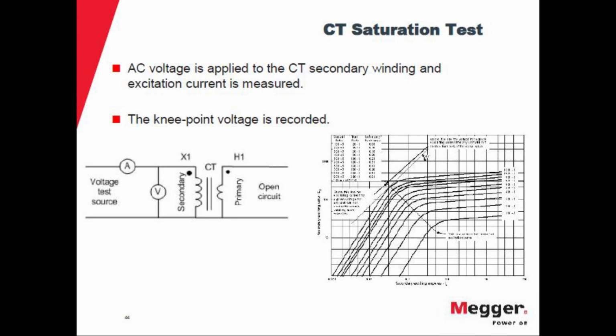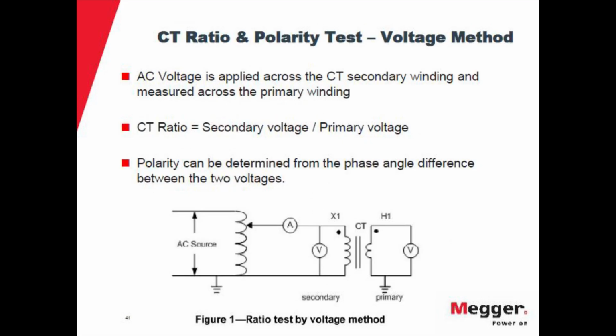So a very important characteristic for the protection CTs, not so much for the metering CTs. In the metering CTs, it's more important to get the ratio. The ratio of the CT is very important in the metering ones, especially to determine if it is within the specs of the accuracy of the CT.